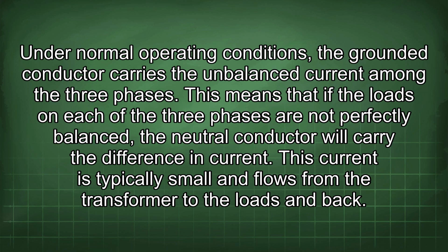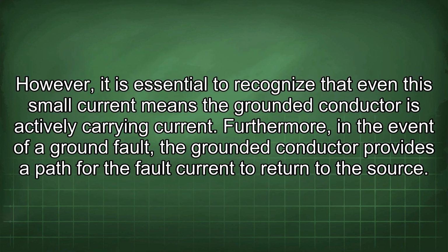This means that if the loads on each of the three phases are not perfectly balanced, the neutral conductor will carry the difference in current. This current is typically small and flows from the transformer to the loads and back. However, it is essential to recognize that even this small current means the grounded conductor is actively carrying current.